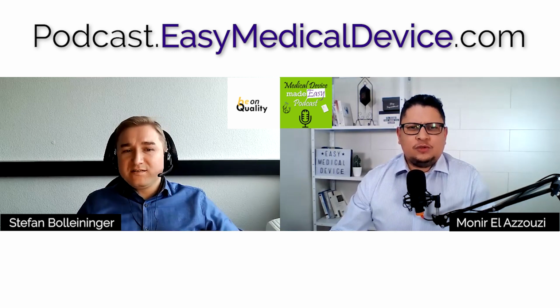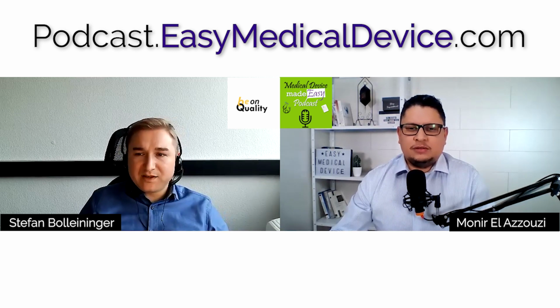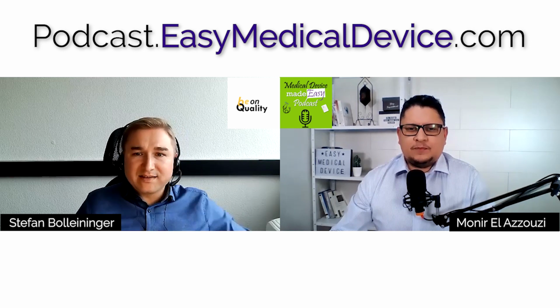There is the good thing. Yes, that the Common Specification is written in a way that it can be reused and taken over by the hospital. So in case, for example, this one is single use, I need a technical documentation. Okay, then you have an abstract, and it's Article 9, which tells you this is what you need to do for the technical documentation. Pretty cool, good from my perspective.